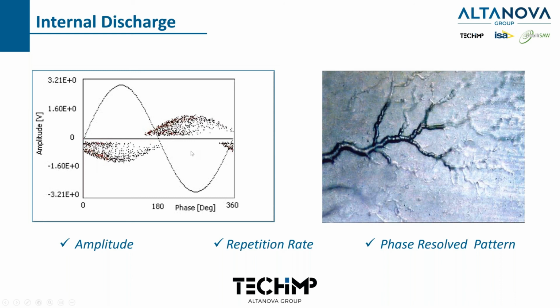This is what it looks like, and this is what the damage has done. These are the water trees I talked about earlier, that are caused by water diffused into the insulation. And then eventually PD, partial discharge, will happen, causing this. And if we pick it up early enough, we can determine if it's dangerous or not dangerous. And if it's dangerous, then obviously you want to replace it before it fails. Again, amplitude and repetition rate will determine the danger level of that PD.